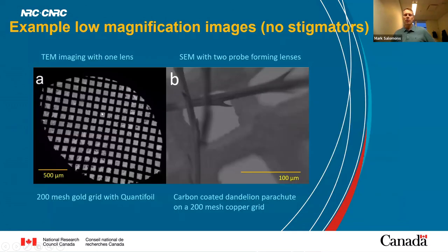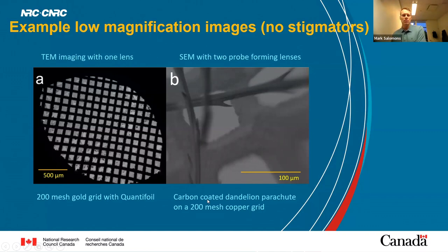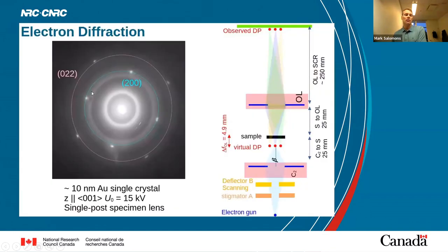Just a couple of initial images — nothing crazy at this point; we've only done a couple lenses in the system. This is just a quantifoil mesh grid, and then we've done an SEM image — we took some carbon-coated dandelion parachutes just to show that we can get images; we haven't done any stigmation yet or cleaned up the beam. We've also done electron diffraction on a 10 nanometer gold single crystal, just with a single post-specimen lens, to show that it can be done.